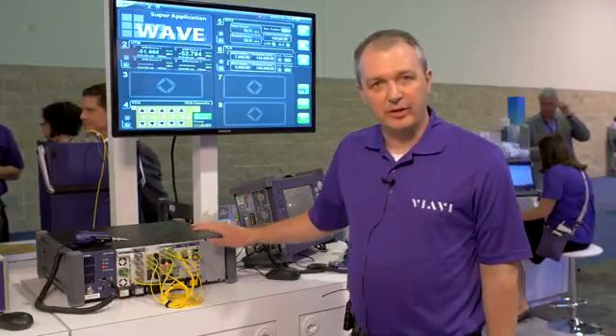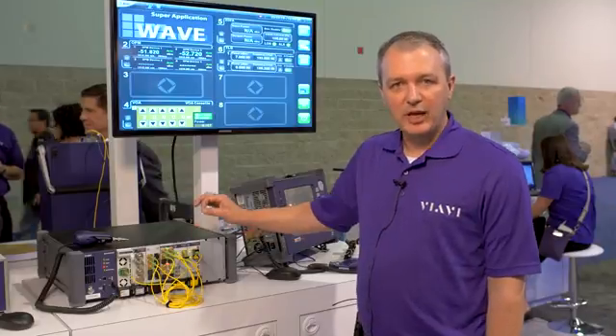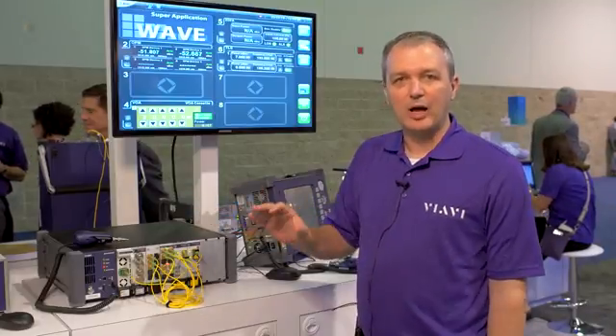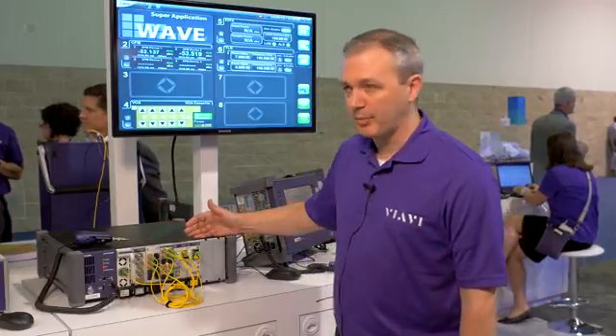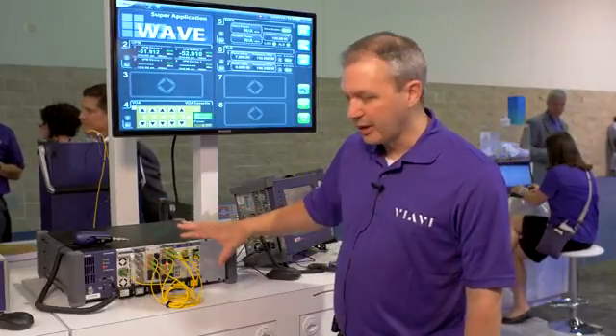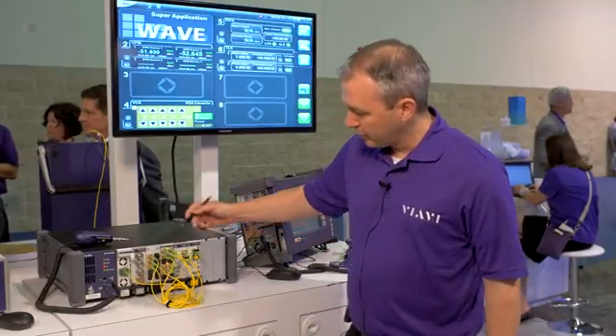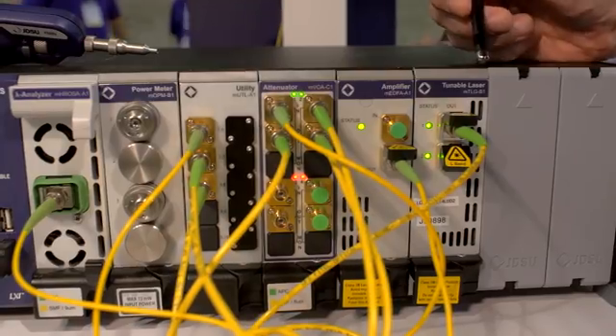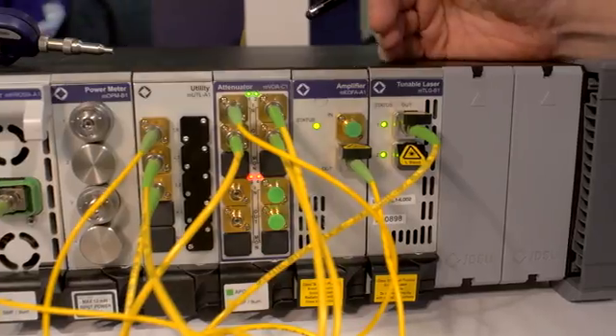In manufacturing today, the challenge is to create a stable, repeatable, reliable source of programmable OSNR. To do that, we're going to use an array of MAP modules combined and interconnected to give you an easy, simple, well-calibrated, stable OSNR generation tool. My first slot has a tunable laser source, which in this case is acting as my simulated carrier.